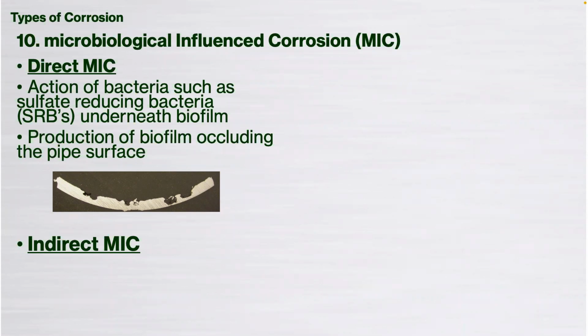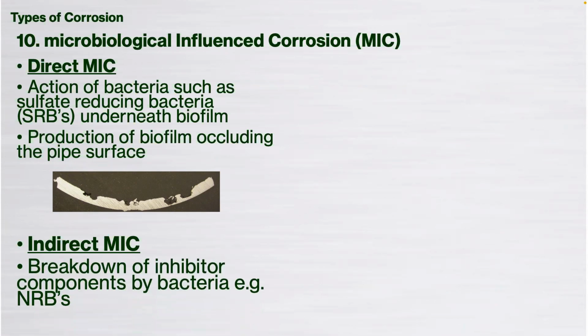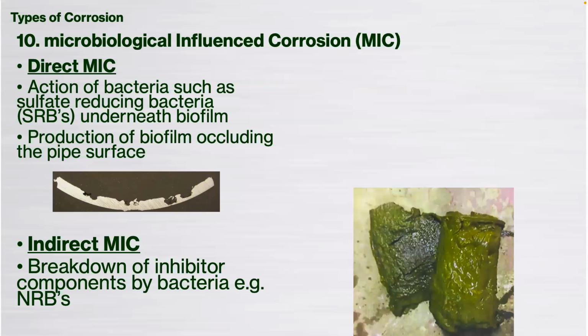The question I asked was what inhibitor they were using, and they were using something called sodium nitrite. That's a food source for bacteria. Once they told me that, straight away I thought to myself, you've had a bug problem. You shut the system down all summer, and that's basically eaten all of your inhibitor, produced plenty of acids and biofilm, and so forth. And then of course you turn your pumps on, and you've got a rapid increase in the level of corrosion in your system, more corrosion deposits, and of course whatever's been created during the shutdown is now causing corrosion as well.